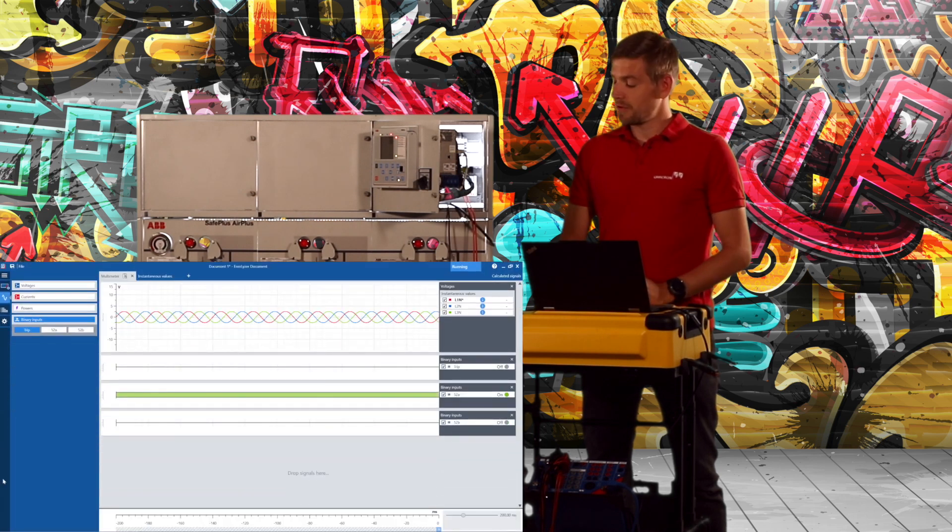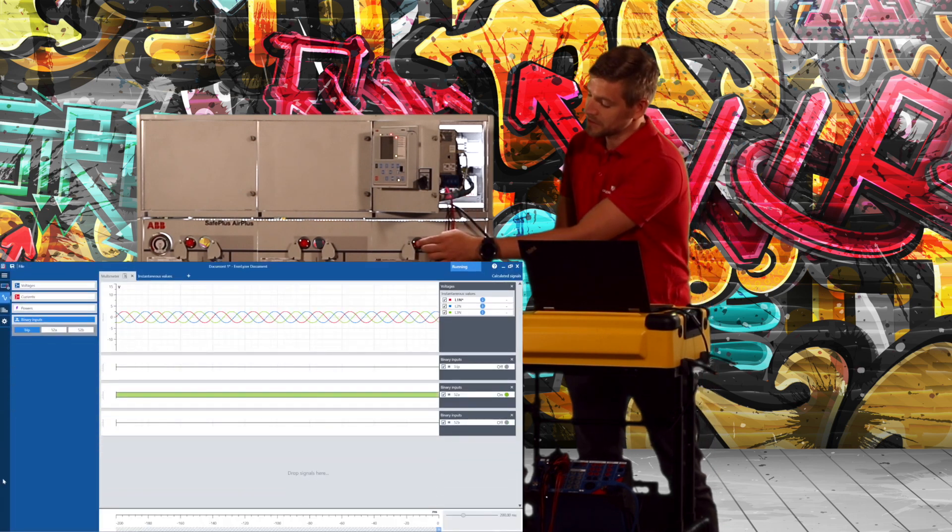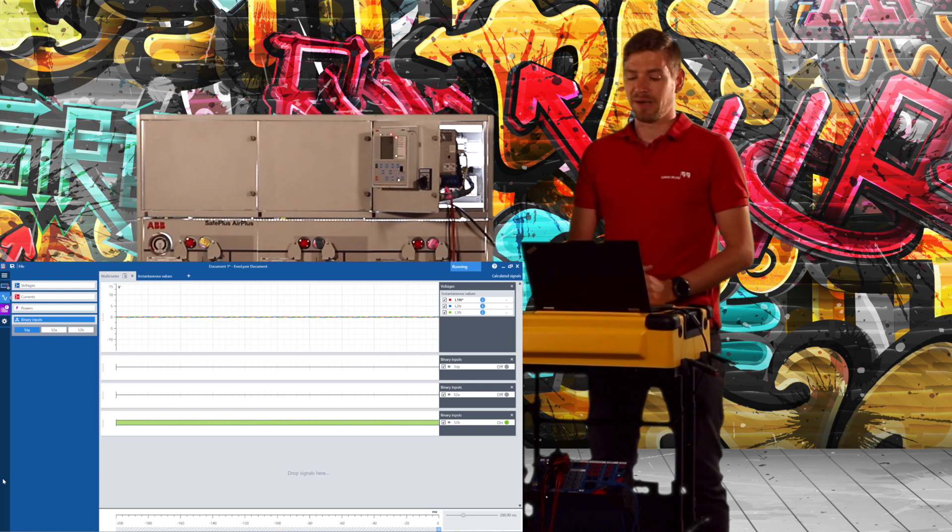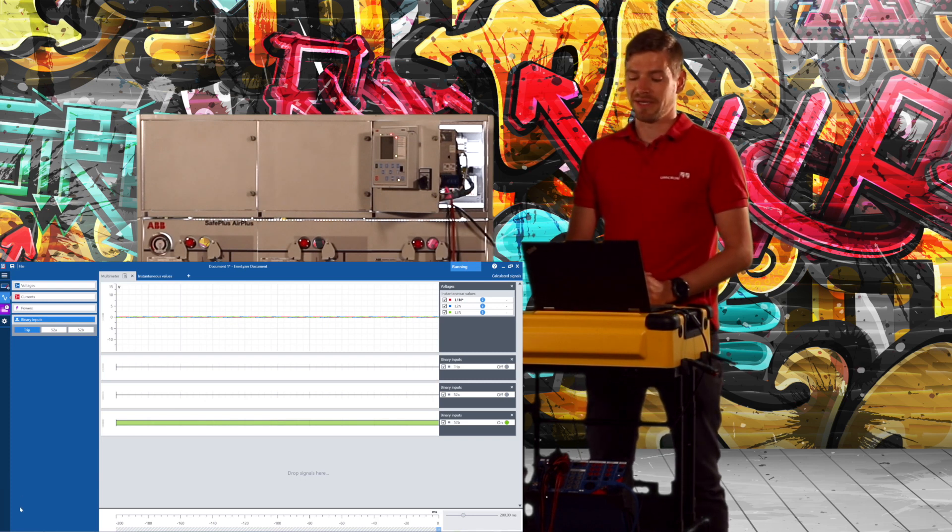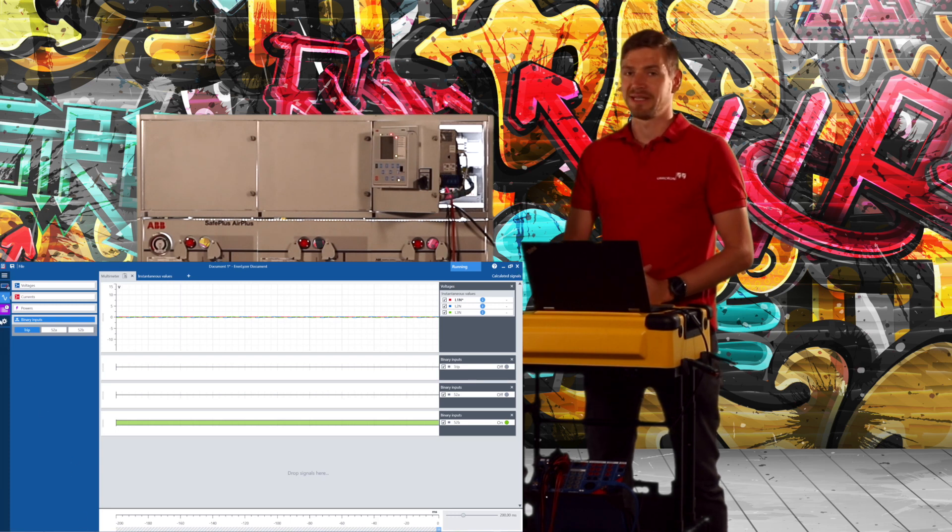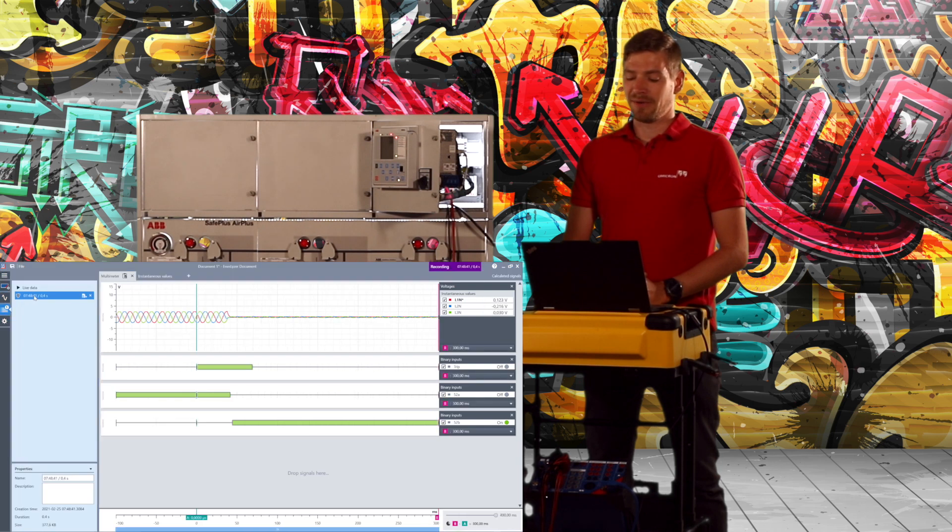I'll switch the circuit breaker off and what I see here now in my test software is that the voltage of my sensors are collapsing and my binary auxiliary contacts are toggling.